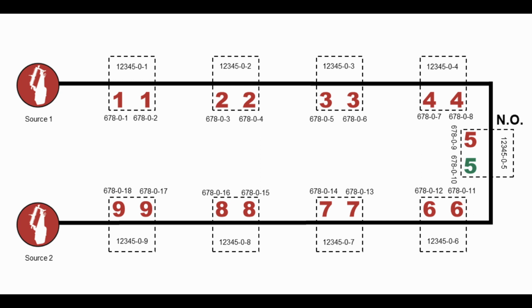Transfer transformer information in the sample loop plan to the EdgeRestore Underground Distribution Restoration System commissioning procedure. S&C recommends starting at source 1 on the loop and commissioning each transformer in order around the loop, ending with the transformer fed by source 2.